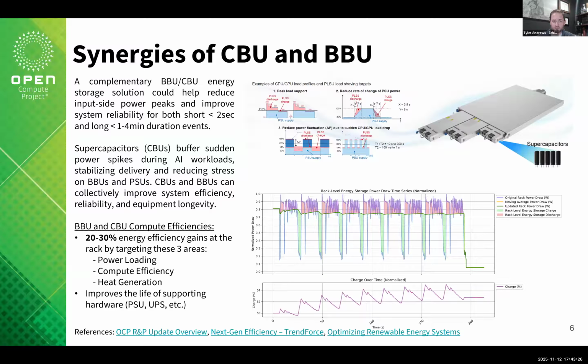The capacitive backup units can only supply that for about 1 to 2 seconds, so it's not for very long, but it's immediate, very high power, high safety, and exceptionally long cycle life. They can run through these high frequency reaction points for a long time, supporting battery backup units, which respond for anything past that 1 second, or potentially top off the capacitive unit once it passes that threshold into the recovery stage rather than the power phase. The point is to have two high power units working in synergy with one another to create a complementary environment.